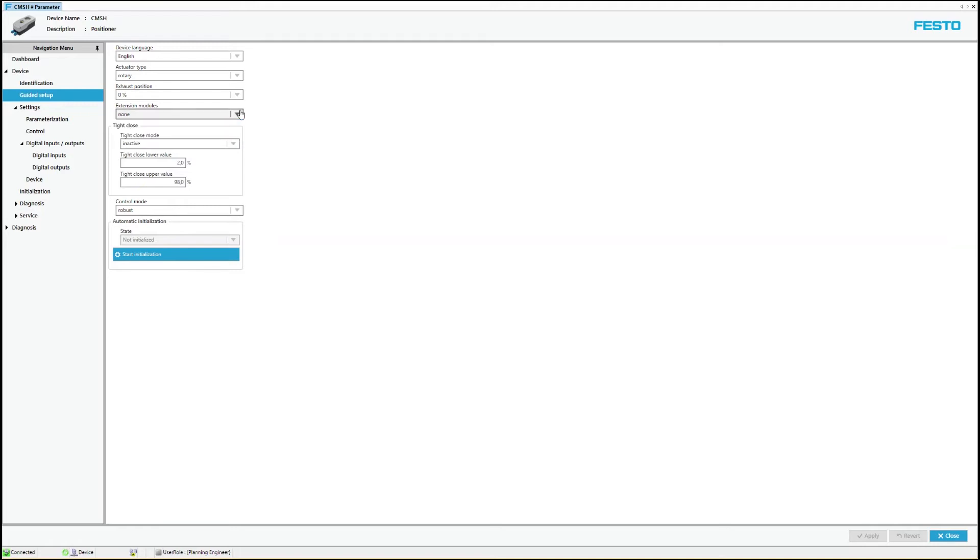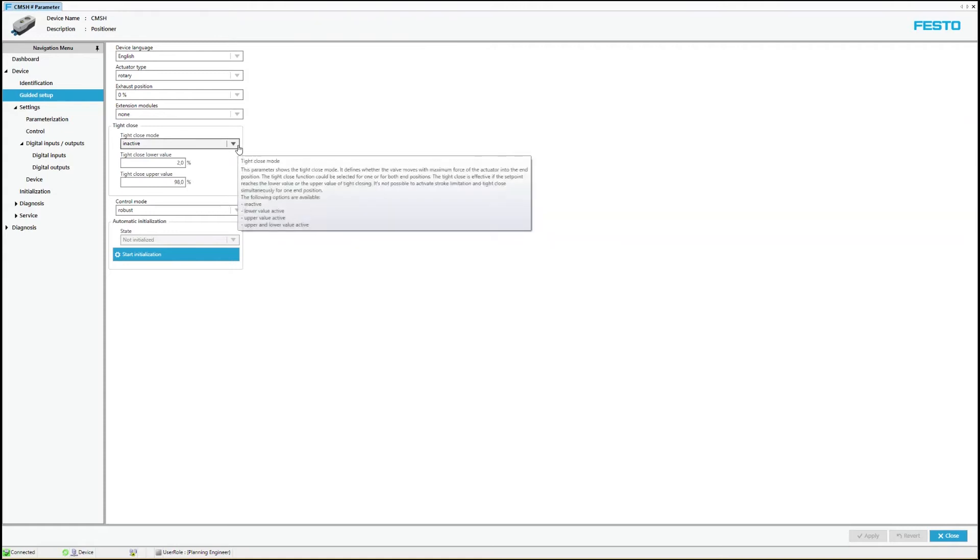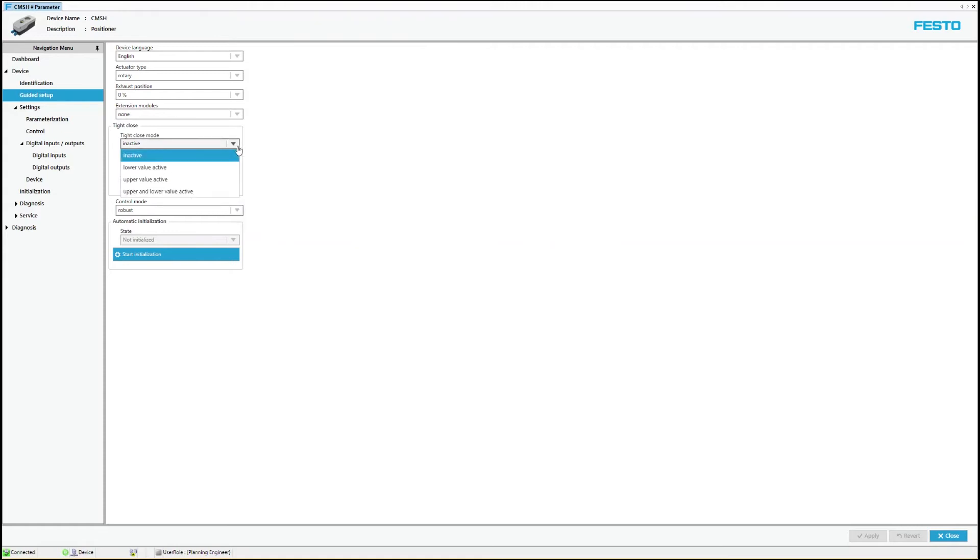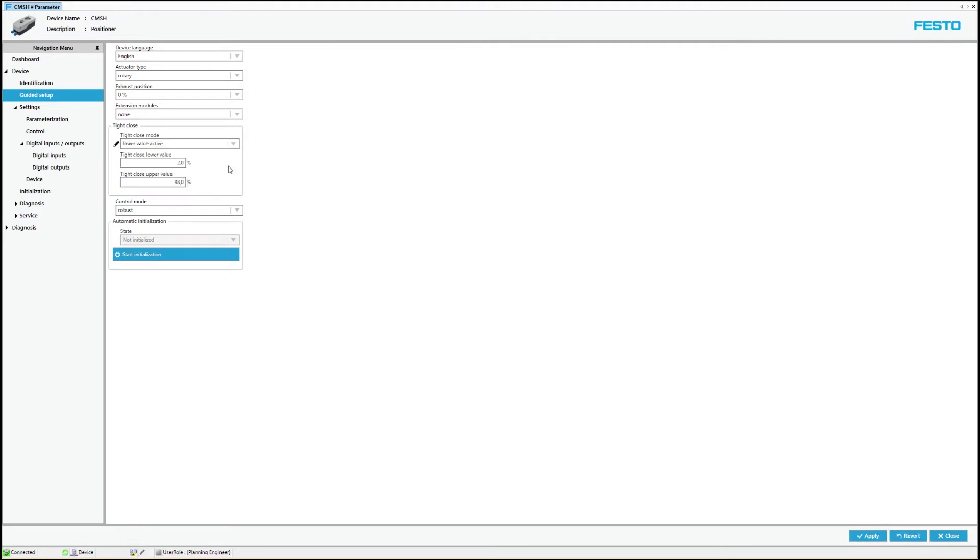In the next step, the tight close can be configured. This determines whether, and if so, at which end positions the tight closing is to be activated. In addition, tight close values can be defined. The lower limit specifies the value below which the setpoint position must fall for the actuator to move to the lower end position with full force.